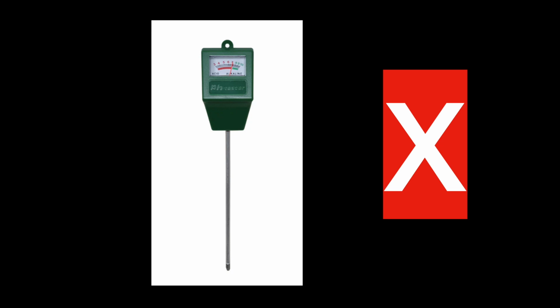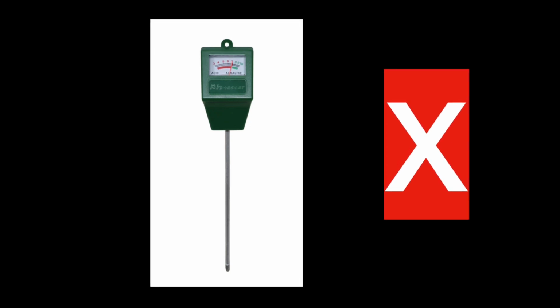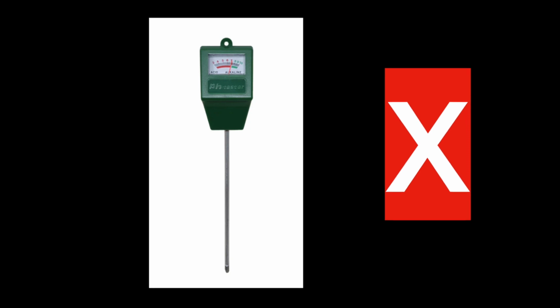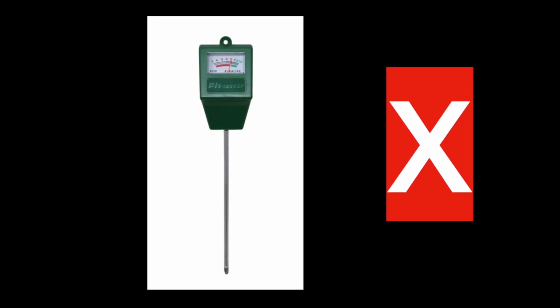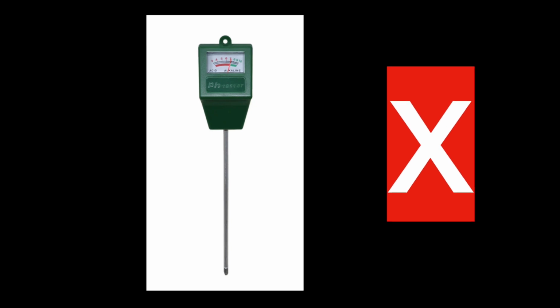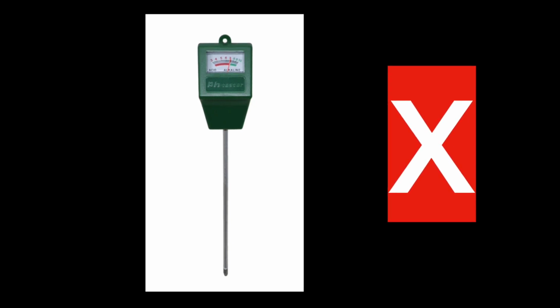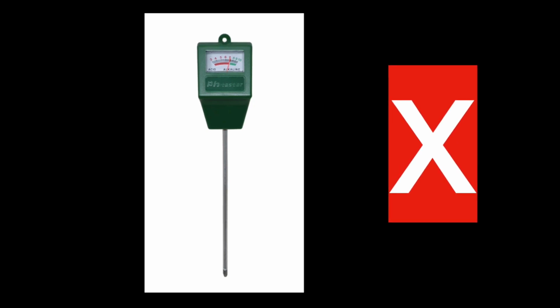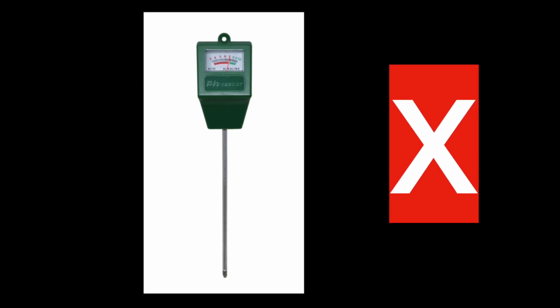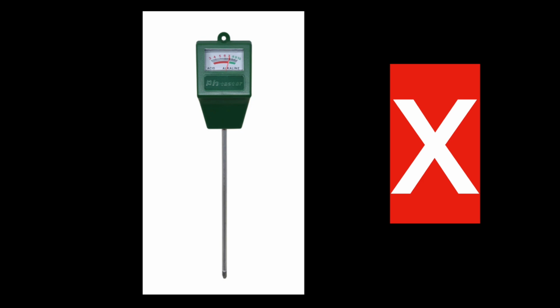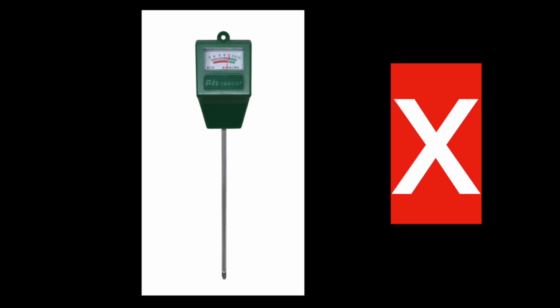You might also have seen pH meters for soil in the gardening centers that look like this, and you might wonder, well, that has a simple solid metal probe, which I can easily clean between different samples. Again, that is really not a solution for you. That probe is not a pH electrode. It is a single metal probe that acts as a battery. It measures electrical conductivity, not the concentration of proton ions. When you stick it into soil or any other moist sample, the interaction between the metal of the probe and the salt ions in the moist soil would create voltage, and that's what that soil probe measures, the voltage.